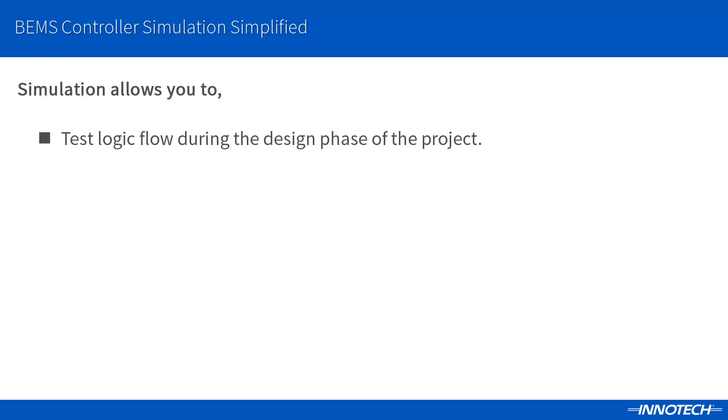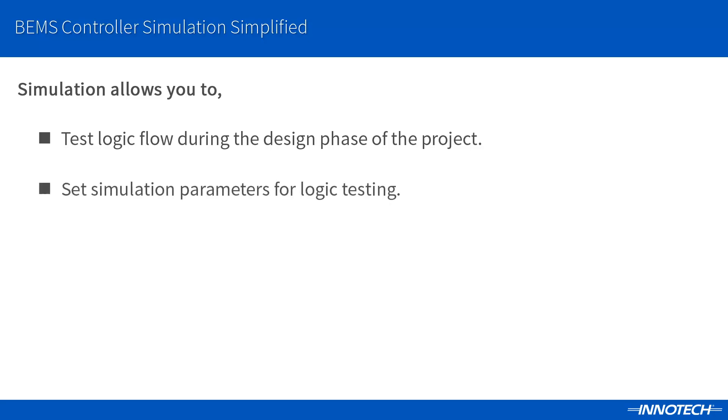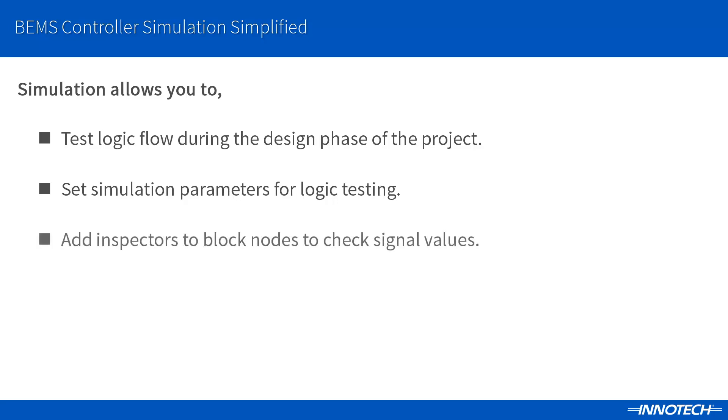Simulation allows you to test a complete controller logic flow and function during the design phase of the controller's configuration, including user adjustments and logic functions. Parameters are available for input and output blocks to simulate functions such as the digital status or temperature sense values, in addition to simulating fault conditions on the programmable UIO points and logic areas of the configuration. We can also add inspectors to the block nodes to view the live values in various areas within the configuration during runtime.